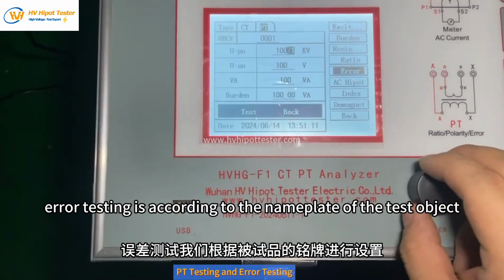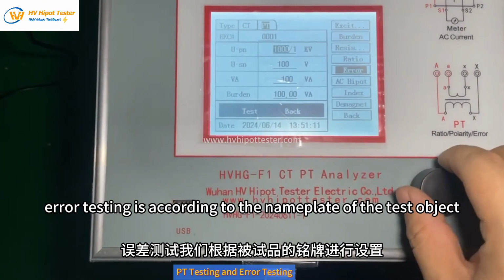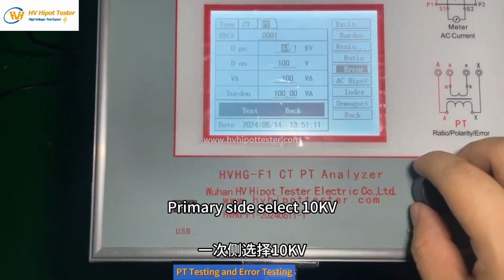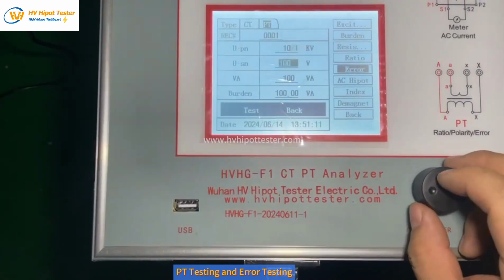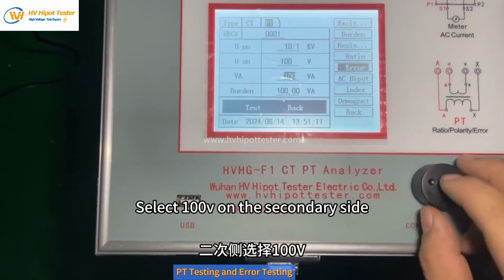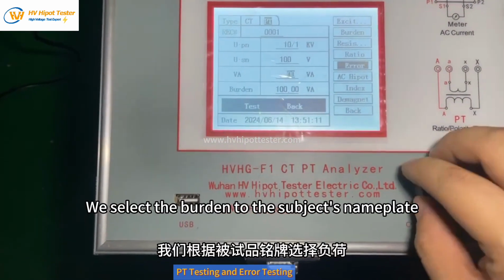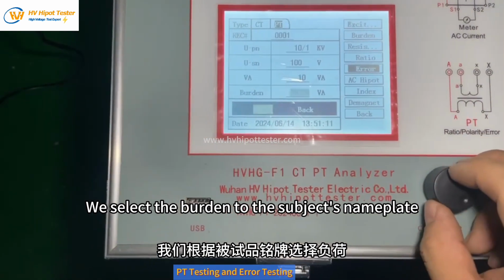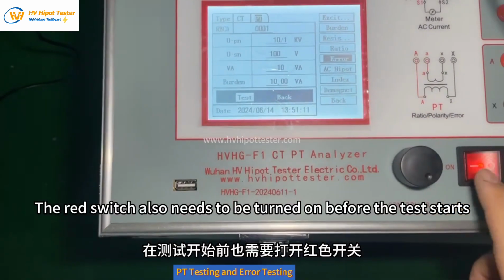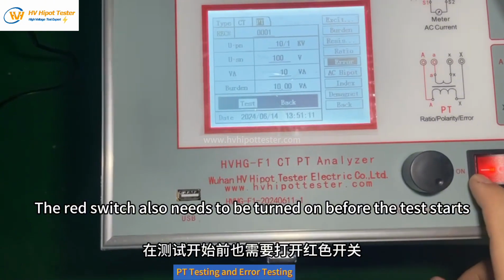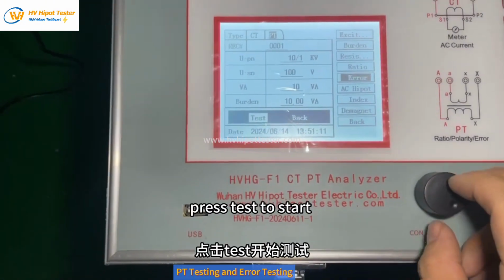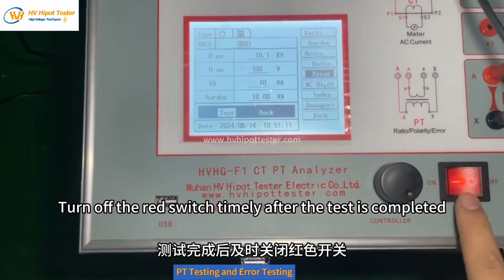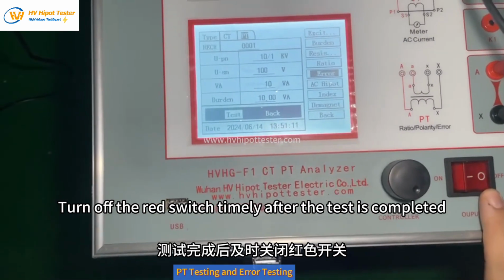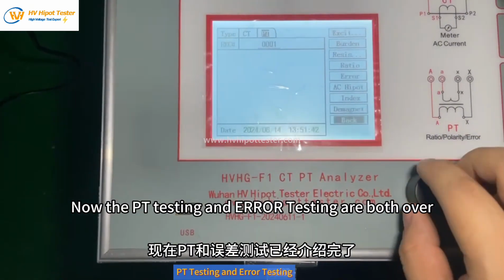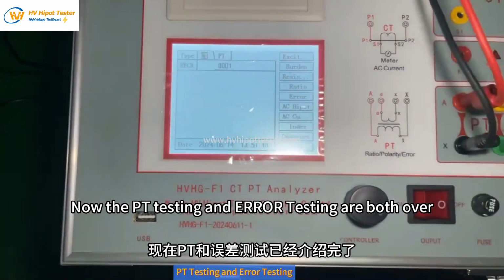Error testing is according to the nameplate of the test object. Primary side select 10 kV. Select 100 volt on the secondary side. We select the burden according to the test object's nameplate. The red switch also needs to be turned on before the test starts. Press test to start. Turn off the red switch timely after the test is completed. Now the PT testing and error testing are both over.